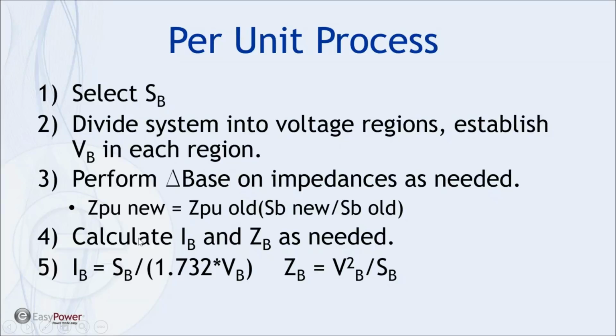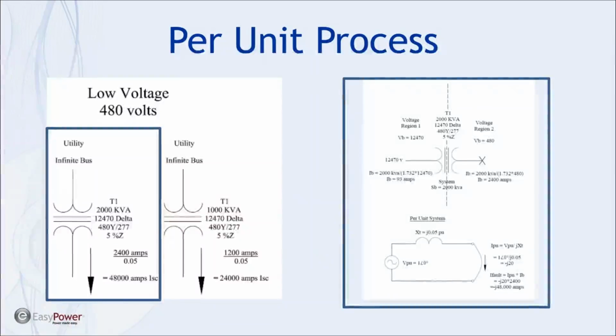Then we go into the different regions and calculate I base and Z base as needed. As I go from an infinite bus configuration today for my utility system and then provide an example utility system, we'll use this Z base calculation one time today. Okay?